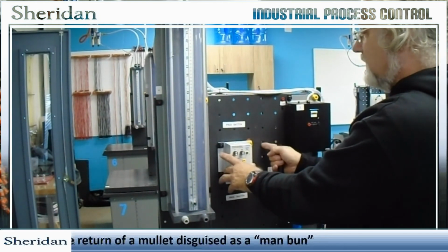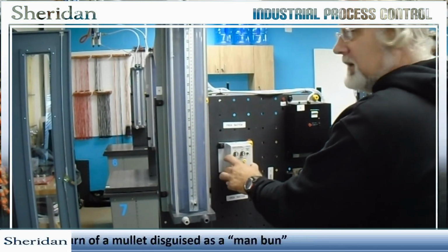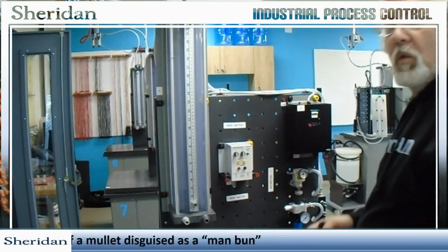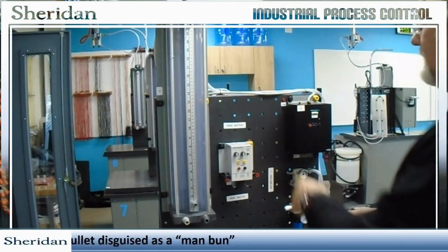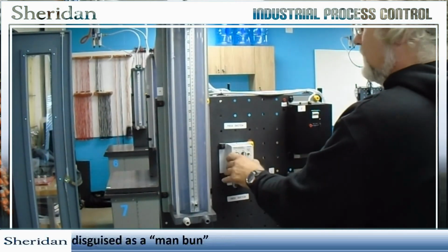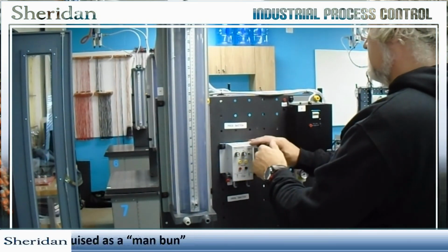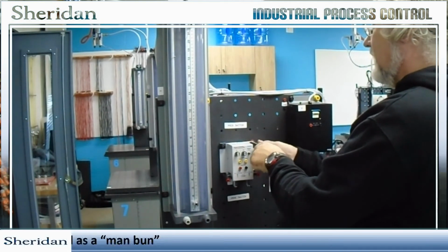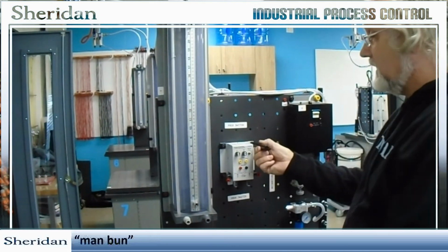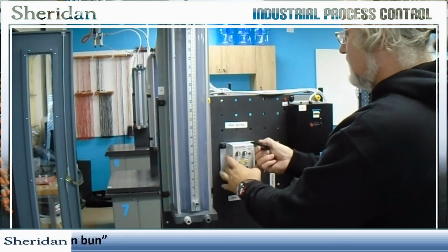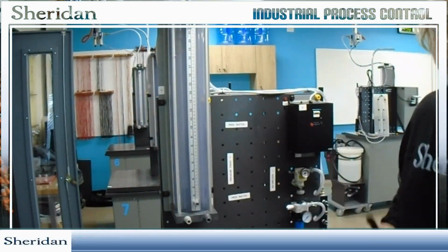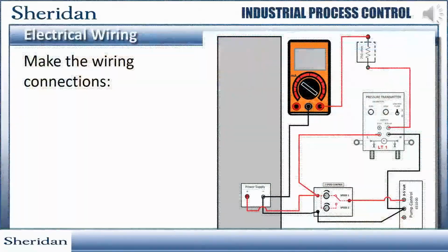So now it's no longer pointing this way, it's pointing up. It shouldn't move. When I go to take it away, I look at that flag. If it won't move, that's a good thing. It should not take any force to give it a 1/4 turn. That tells me the direction I'm going to move the unit to remove it. It's just that simple. Now that the device is mounted and cleared, you can proceed to the signal wiring.